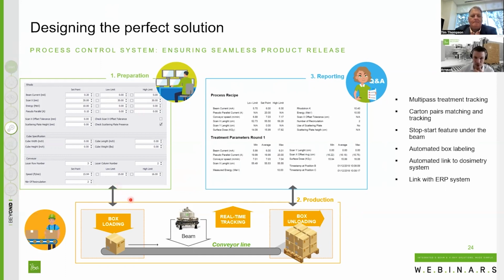Then the operator will load the box. The system will automatically do all of its things, irradiating the product and making it recirculate the number of times that is needed. And in the end, we have a report that will show that the process parameters were in control during the whole irradiation of the product. We know exactly how much dose it received. We have dosimeters going in the system at frequent intervals so that we can make sure again that the dose matches what we expect it to be.